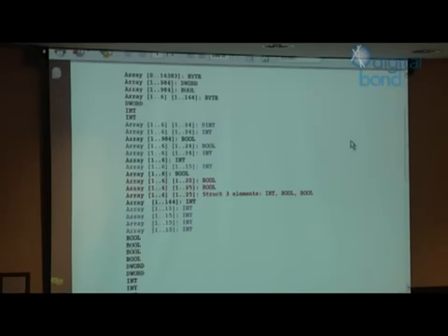And we see something else here. For example, we have this structure with 24 entries. This fooled us for several weeks because we thought it would have a relation to the plant configuration, but it doesn't. It's just a memory table that's used for indexing into another address table where I/O addresses are stored. But this is important here. This is the reason why it's highlighted in red. So we have other structures with 25 entries. And they're absolutely central for the attack.